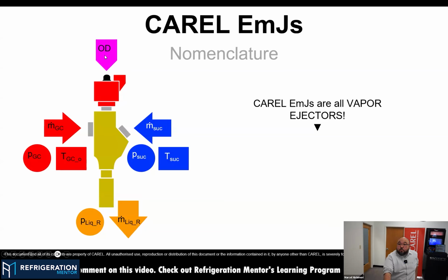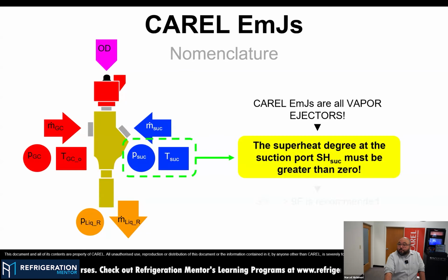And in our case, we also have a third variable, that is the opening degree. Since we have an ejector that can open and close, we can control this mass flow, controlling the gas cooler pressure at an optimal point, even during summer conditions. And this allows the system to control the pressure and, as a positive effect, drag refrigerant from the medium temperature lines, okay?